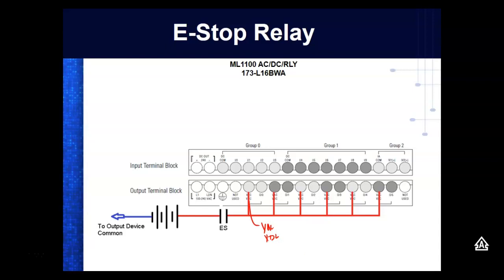So you can determine whether you sink or source. It depends on how you hook up the common, right? You understand? Relay switches have no idea. So normally when we wire wall switches, the basic way is to put the hot on the top of the switch, but you could switch it around, and it would still work as a switch. It doesn't care if you put AC on it or DC on it. So these are relay outputs.